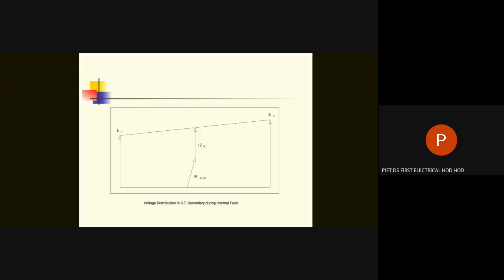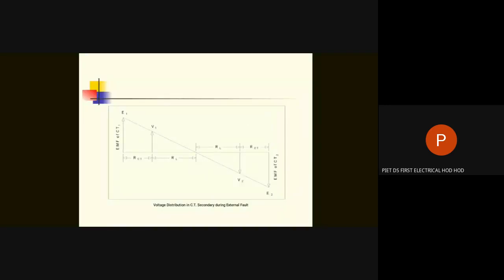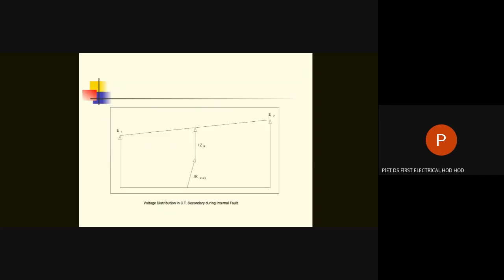The next slide is showing the internal fault. For internal fault, E1 and E2 have the same direction. A large current I flows, and I times ZR is the voltage drop across the relay, where I is the current flowing through the relay, so the relay will certainly operate. And to avoid the large voltage across the relay, we have to drop some of it across the stabilizing resistance. So I times R stab is the voltage drop in the stabilizing resistance. So this is the diagram. This vector diagram is for external fault, and this diagram is for internal fault.